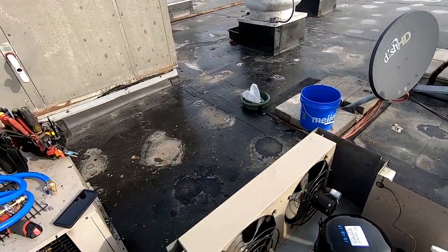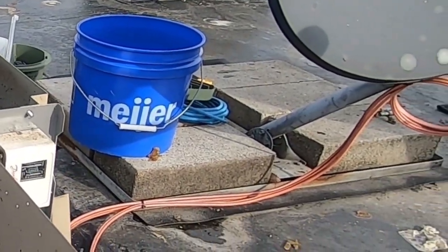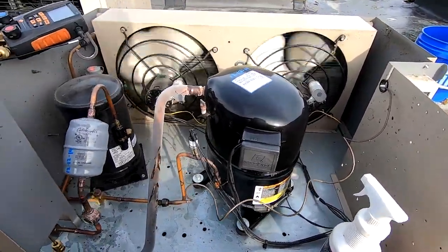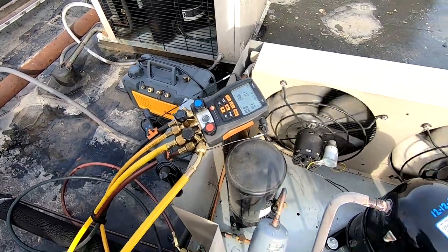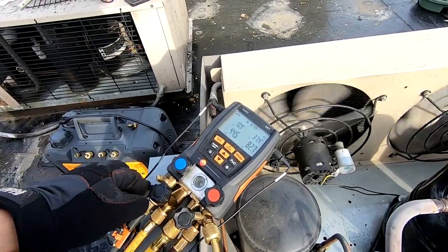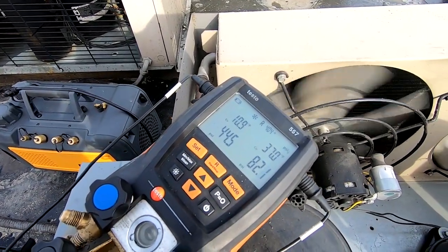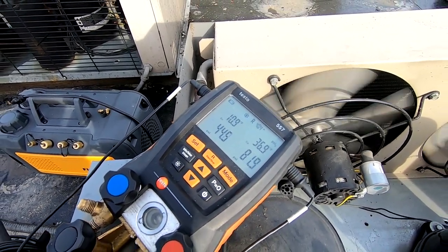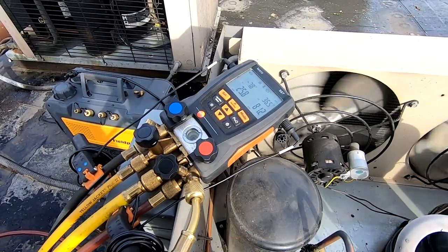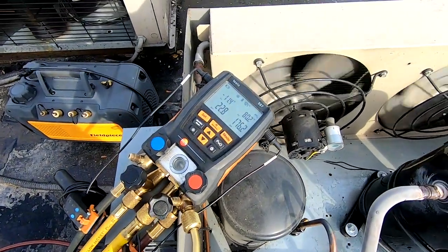Outdoor temperature out here is about 20-some degrees. We've got a 180-degree head pressure control valve. We're going to make sure that low pressure control is kicking out like it's supposed to. Not sure exactly what took the compressor out, but not going to take any chances, so we're going to make sure everything's working the way it should. That's not good - my gauge blanked out on the suction side. That's lovely. Sight glass is full, head pressure's really low. My valve's off - there we go, that looks a little better.